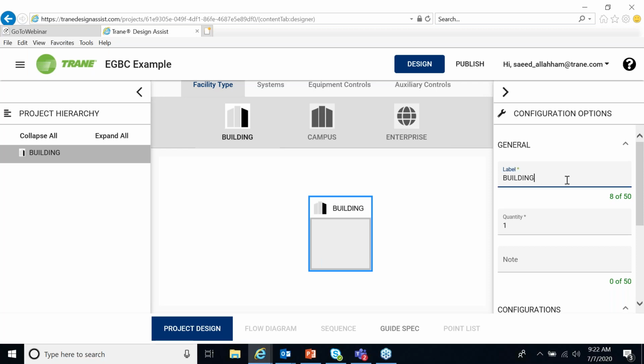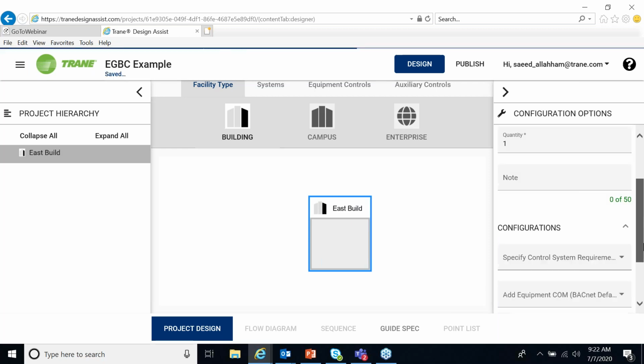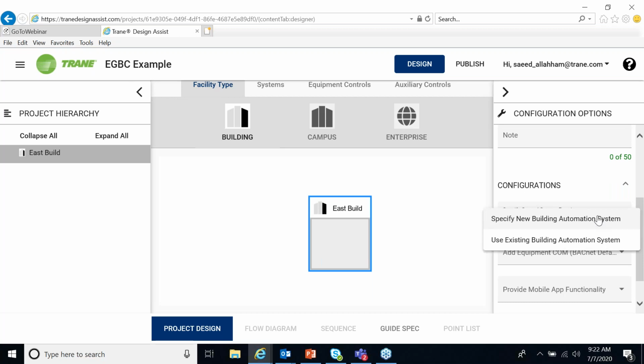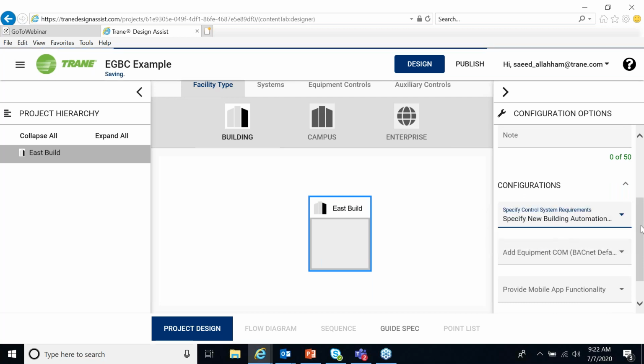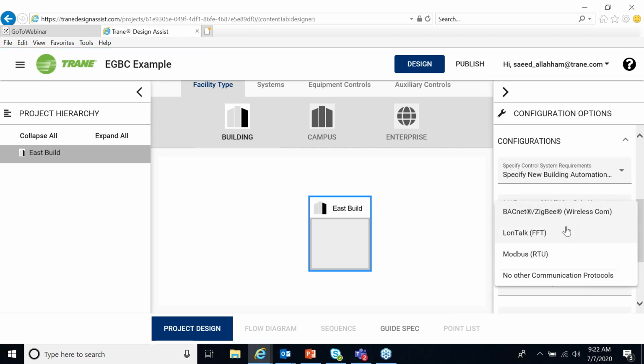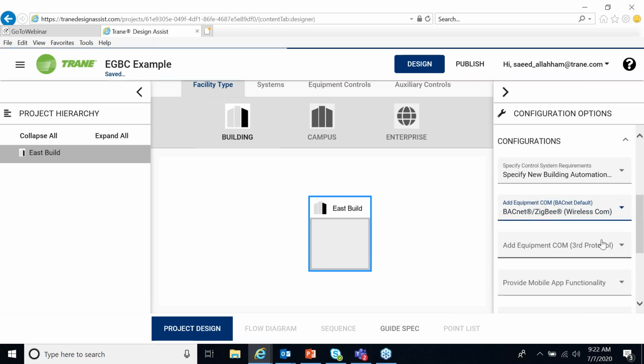Now we can call this one East Building. We have how many quantities? We have one. And the configuration, we can specify the type of the control. Is this a new building or an existing building? For example, let's say this is a new building. And let's say the communication, we can say BACnet, non-Modbus, let's say BACnet.